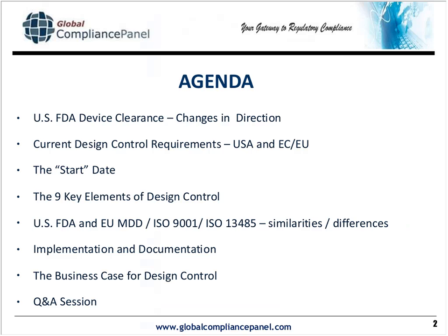Now, design control, especially for developers, is a key issue with the FDA. For those of you that have been audited by the FDA, you know that medical device companies are audited generally under the QSIT model, Quality System Inspection Technique. That focuses on 7 areas of the GMPs and really drills down to 4 key areas.